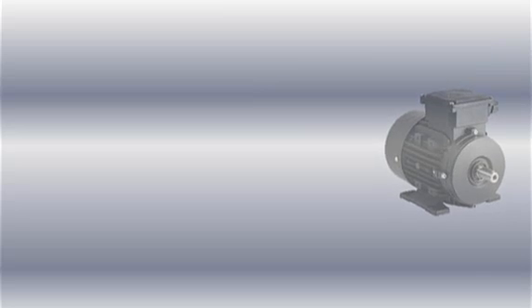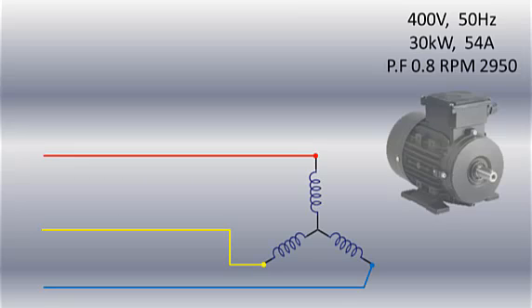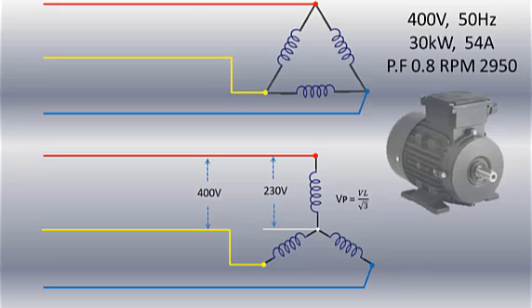Here is a three-phase induction motor with a nameplate rating of 400 volt, 30 kilowatt and 54 ampere when connected in delta. However, if the motor is connected in star configuration, the voltage across each winding will be reduced by a factor of square root 3, about 57 percent compared to the line voltage in delta connection, because in delta, line voltage is equal to the phase voltage.